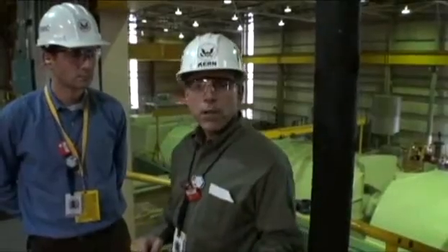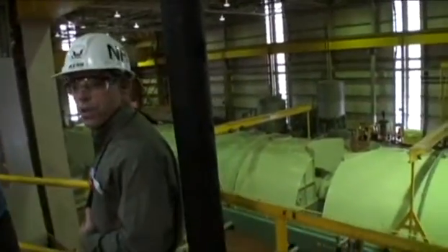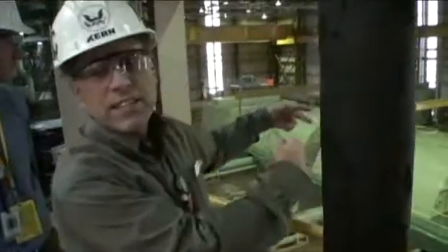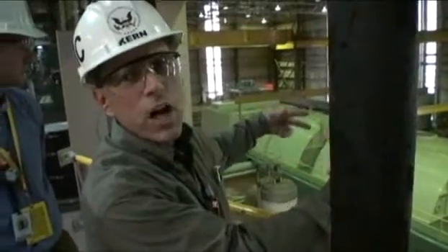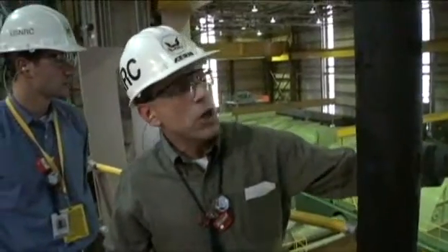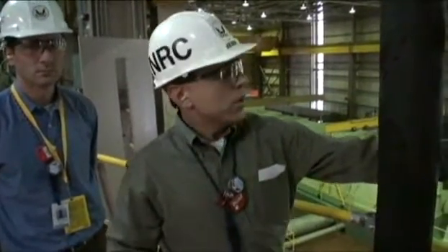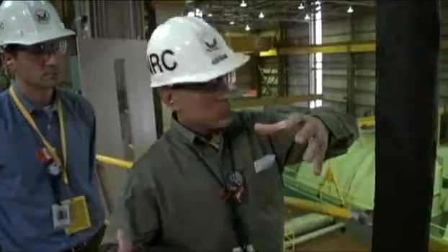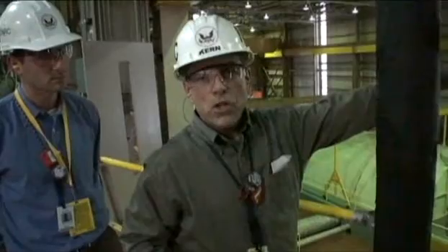What you're seeing behind me, behind Justin and I, is the main turbine for the station. High-pressure steam at approximately 900 pounds of pressure rotates the turbine at 3,600 revolutions per minute. On this end of the turbine, the mechanical motion of the turbine is transformed and generated into electricity. Large electrical cable buses take the electricity out to the off-site distribution grid, where it is further distributed to businesses and homes in the area.